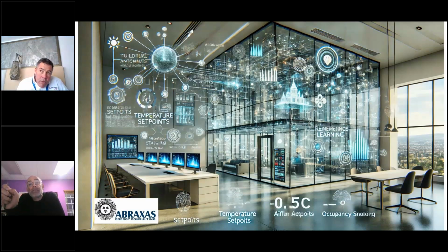Is that correct? Quite possibly, yeah. Quite possibly, because the energy efficient operation of a chilled water plant has a little nuance to everyone's sequence. We start with Guideline 36, and we look to the high performance sequences of operation advanced by ASHRAE, that's really our standard setting organization. Every building is a little different, and it ages differently. I've been advocating for conductivity sensors on the chilled water plant loops forever, and it always gets value engineered out. I think it'd be really interesting to trend and track the water chemistry values in the central plant and compare that to chilled water or chiller plant efficiency over time. We suggest it on the front end, but we get value engineered out. I think now we're going to see greater interest in greater point densities, because there's a curiosity to monitor more things that can consume and impact the efficient operation of these systems.